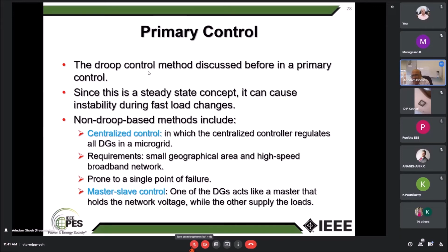The other one is called master slave controller. One DG will act like a master and hold the network voltage, and the others will supply the load. It's sort of like the concept of load flow, where one generator sets the angle and the others supply the load. It's a little bit more refined, but this also requires a communication network. So even though these methods are implementable, the Droop control method relies only on local measurement, so it is more reliable. And you add the secondary controller with that.